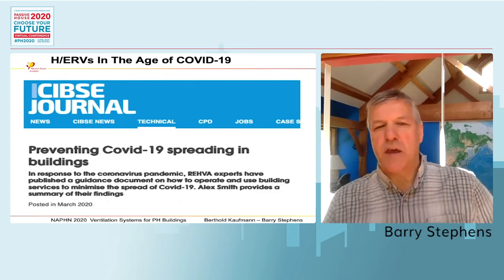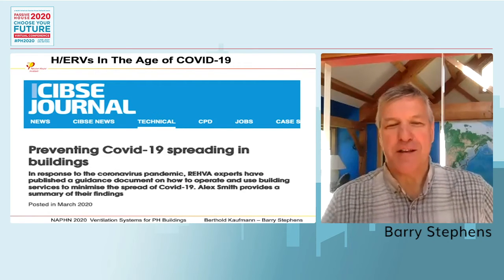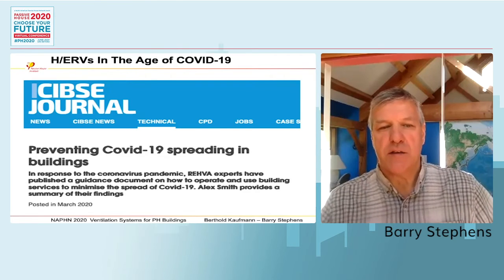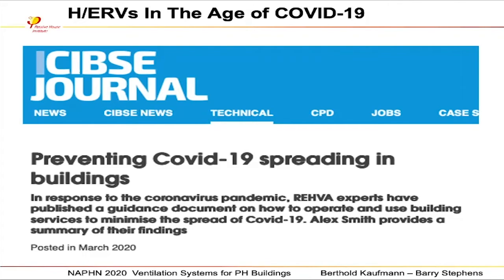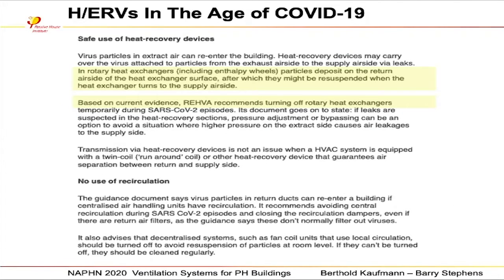I'd like to expand on that a little bit because in the age of COVID-19 and virus spread, this has become a very big subject. And this is a journal, actually a European engineering journal, and they shared some guidance for ventilation in buildings. A couple of big takeaways: with these heat recovery devices, one of the factors that we saw earlier is that the wheels have moisture adhere to one side of the wheel. That wheel then turns 180 degrees and the air goes in the other direction. So in the case of exhaust air with moisture in the wintertime, the moisture adheres to the wheel, the wheel turns, and then the incoming dry air picks up that moisture and brings it back into the building. That's how wheels work. And they also transfer heat the same way.